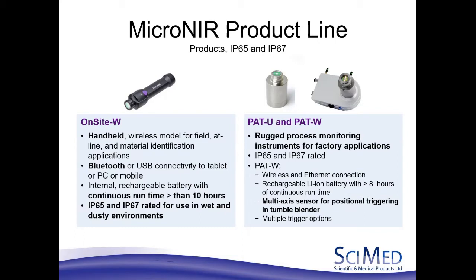The PAT-W is a wireless instrument, hence why we're talking about it today. It fits in very well for tumble blending, but also has the ability to connect via Ethernet if you want a static measurement position, connecting via Ethernet and power. Again, the battery is an 8-hour battery, so it will generally last longer than the process itself. It also has an inbuilt multi-axis sensor, which makes it ideal for triggering in applications such as blending.